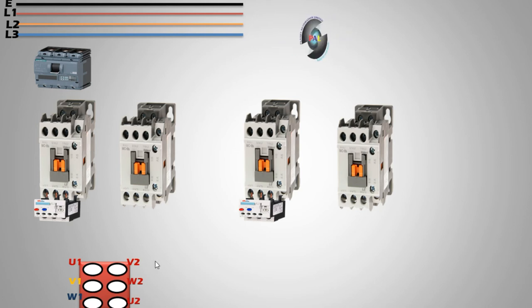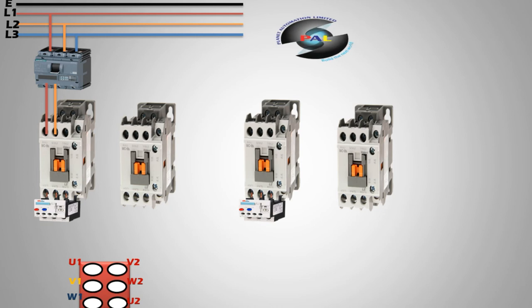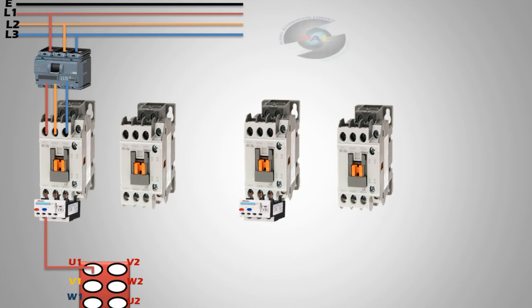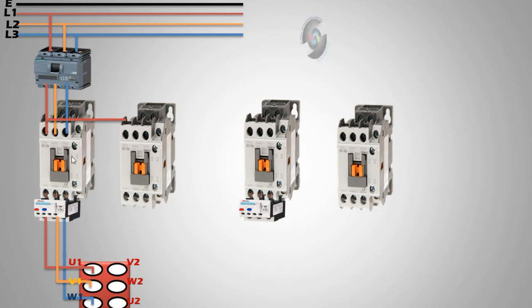This part is for delta only. The terminal U1, V1 input is the same; the output is the delta controlling connection. Now connecting our three-phase circuit breaker and three-phase line in MC1 for forward — through the overload relay one — to the main magnetic contactor for forward. The output is directly connected to U1, V1, and W1. When supply is activated, the magnetic contactor activates and the motor runs in forward.